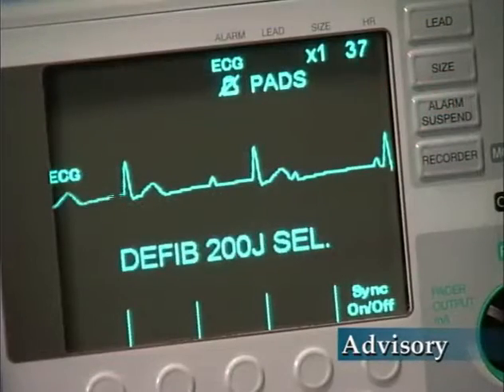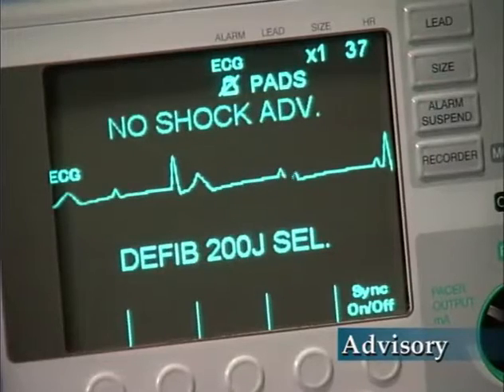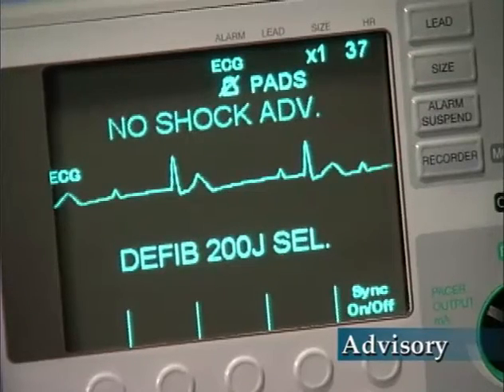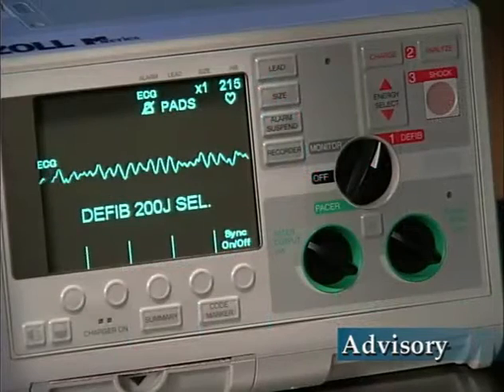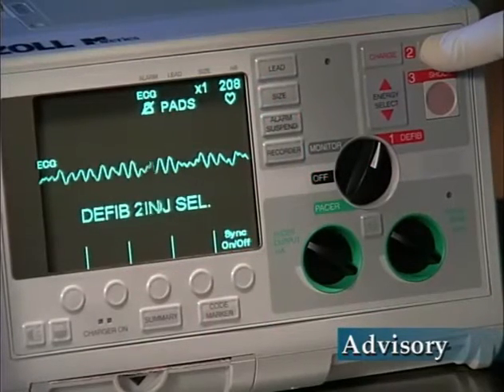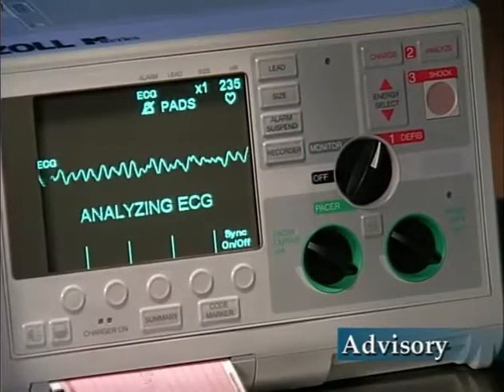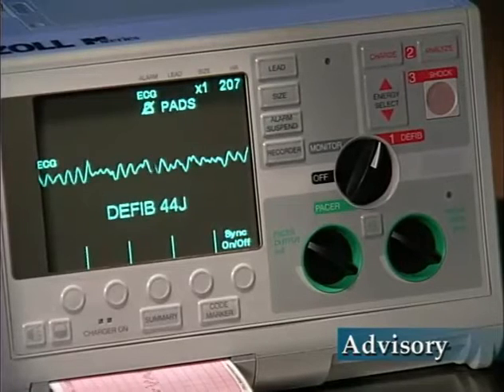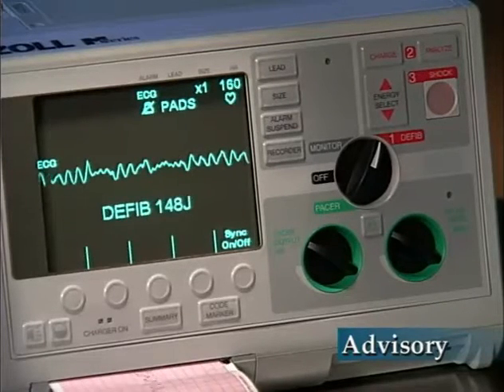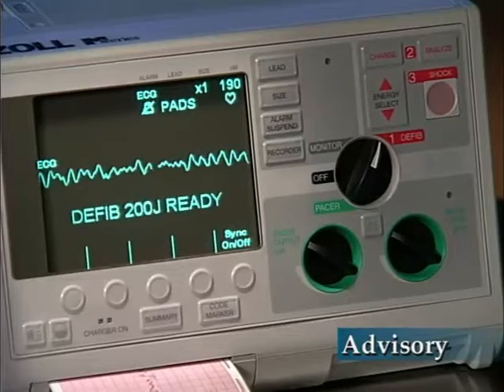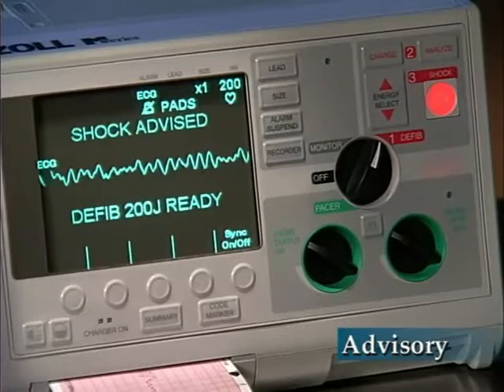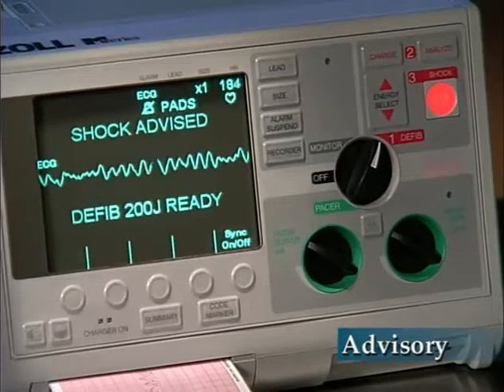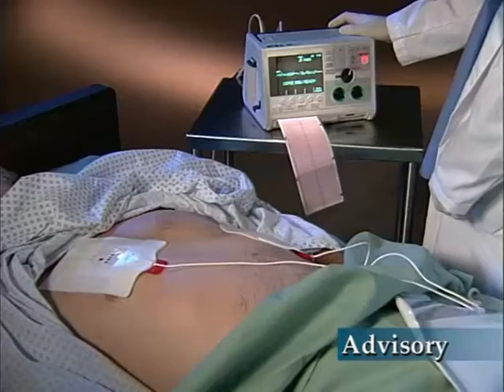When a non-shockable rhythm is detected, a No Shock Advised message will be displayed. When a shockable rhythm is detected and a shock advised message is displayed, charge the unit as indicated by the prompts. If the automatic Analyze and Charge option is enabled, the unit will automatically charge to the pre-configured or user-selected energy setting. The shock button will light up, and a continuous tone will sound.